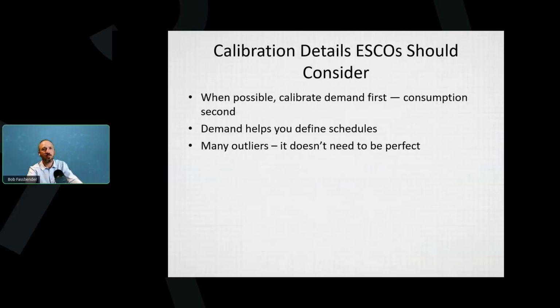One other calibration detail that performance contractors should look at is to look at demand first and then consumption second. If you can look at demand month to month, specifically electric demand, that can help you identify schedules. You can also find other things that are probably going wrong with the model if there's an outlier in a certain month. Again, it's probably an opportunity to save quite a bit of money. In terms of the model, calibrating demand helps you define better schedules, or you can find if there's a big peak during the day where everything's on at once. There are different ways to do that.